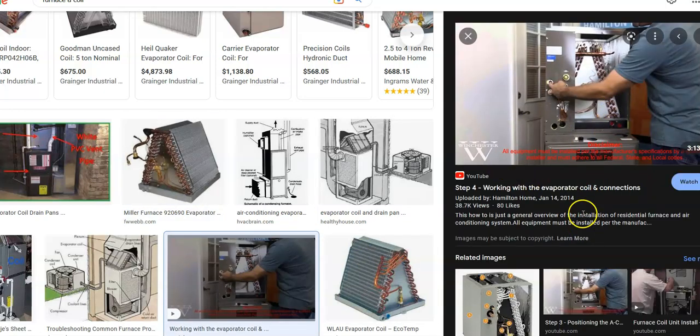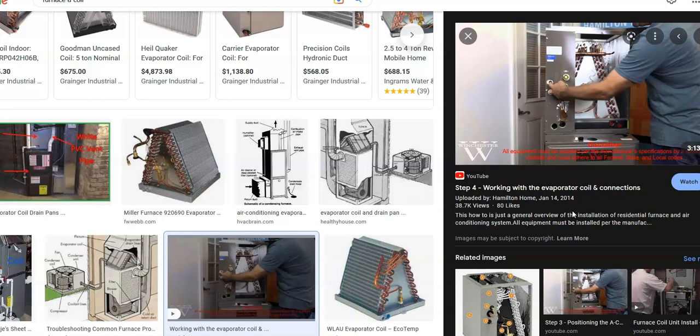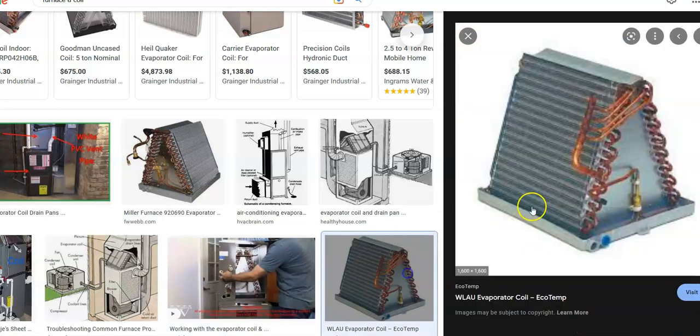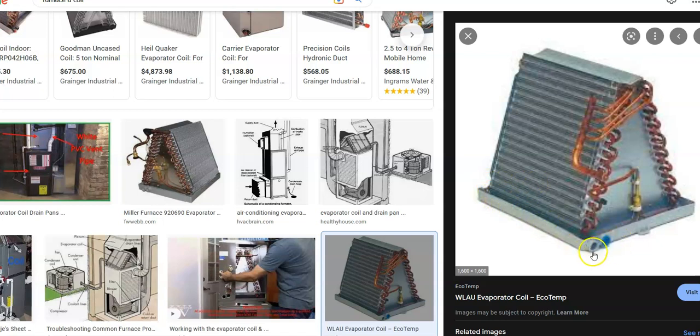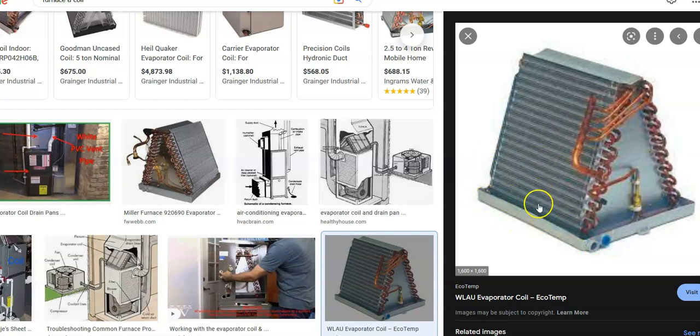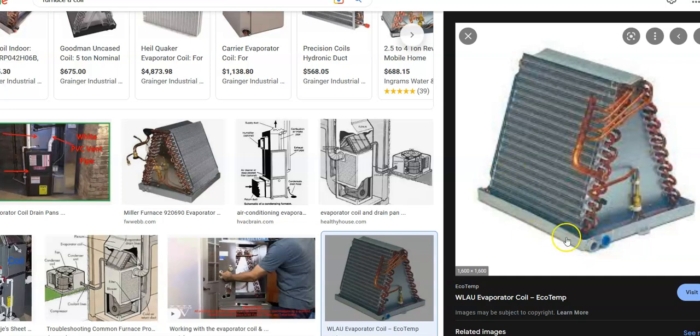The reason they leak is because like all air conditioners, when it gets humid out, they pull moisture from the air. Condensation will build up on this A-coil and it'll come down and leak. Now this is normal. There's nothing wrong with this thing building up condensation. All air conditioners do this. But there's a drain line that takes care of the water. You can see in this image right here at the bottom, all the condensation will drain down and drip down and come into this bottom pan. It'll come out through this drain tube right here.